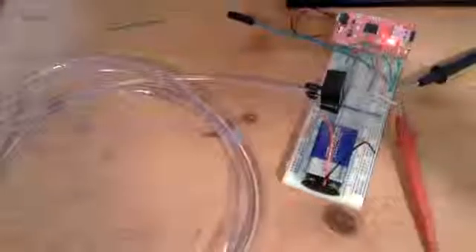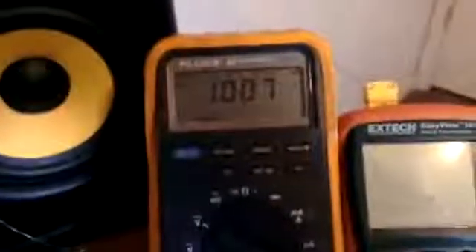So in order to calibrate the pressure transducer, what we need to do is we need to get the tube that is listed in the materials. When you fill that completely up with water, then hook it up to the bottom sensor of the pressure transducer. So right now we have all the water at the same level, and we're measuring the output voltage across the output of the pressure transducer, and that comes out to be about 1.007 volts.